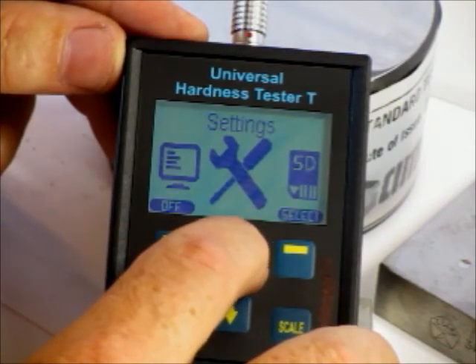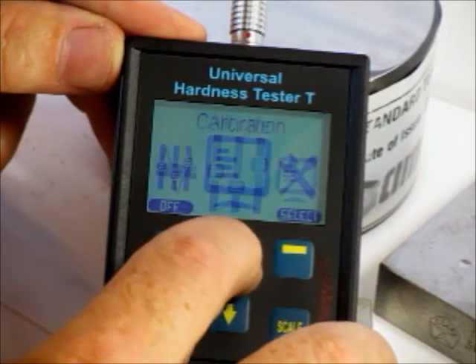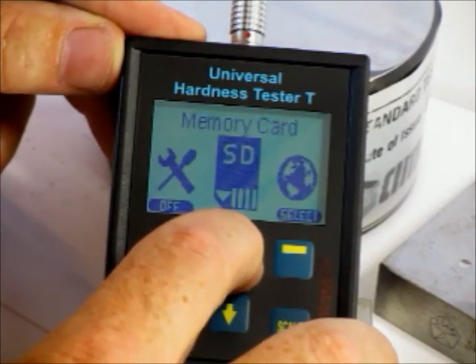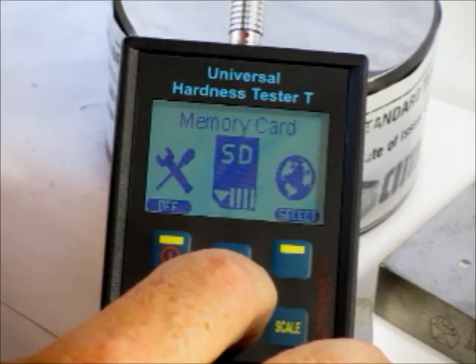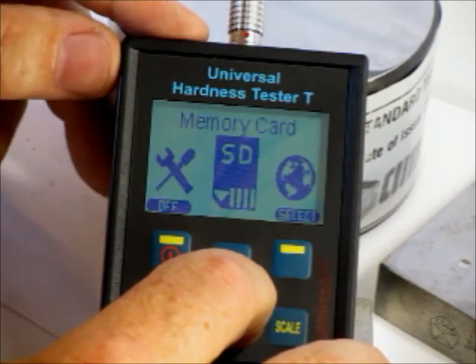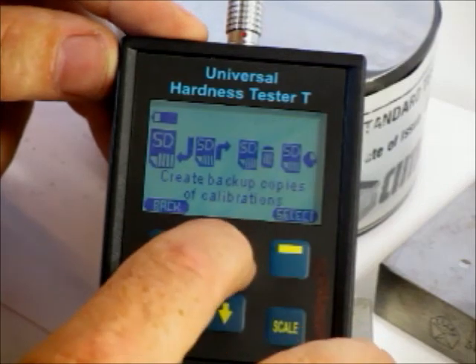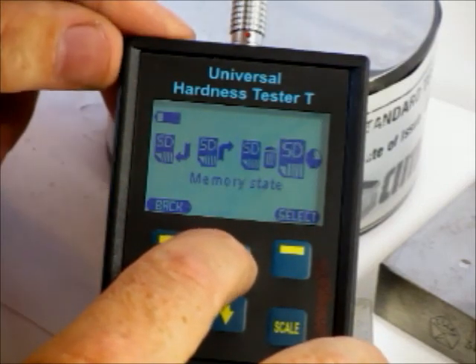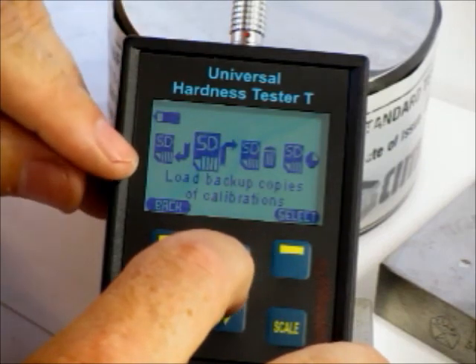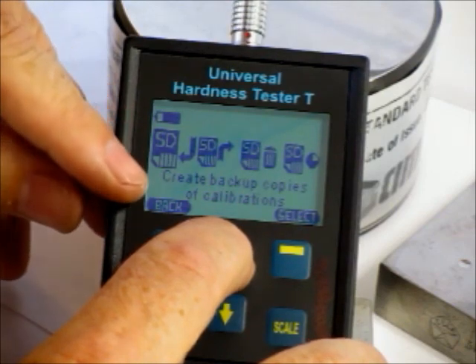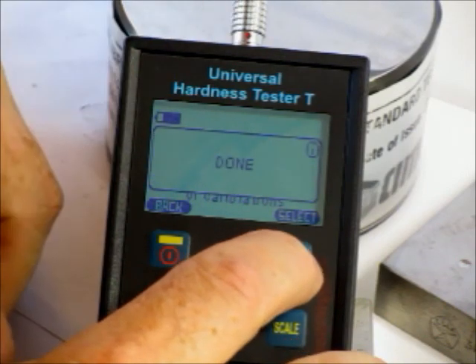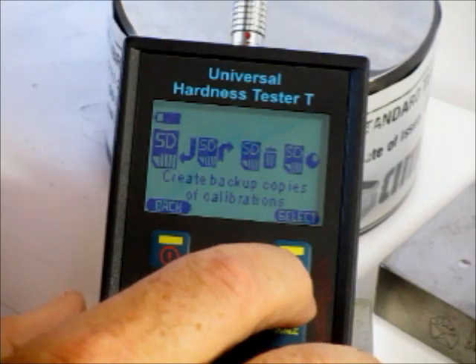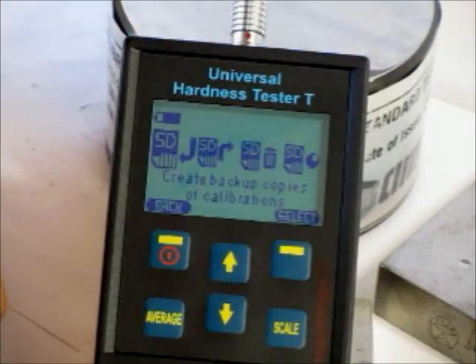The other thing I might want to do at this stage is to save back to my memory card, in other words to save these results back to the probe itself because it has its own memory, is to use the arrow buttons and do a load backup copies of calibration. This first one here is to create a backup copy of calibrations. Hit select, so it's the first one in our line here. We hit save, and now we've saved to the probe the calibrations for these test blocks. So it's as simple as that. Thank you.